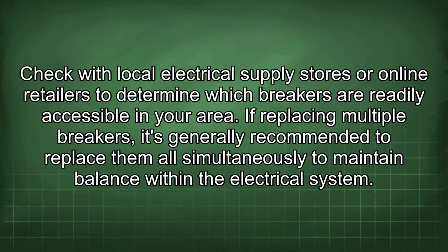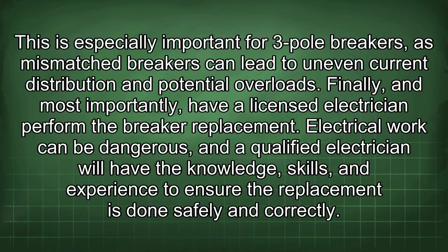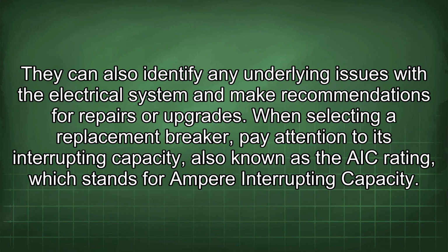Check with local electrical supply stores or online retailers to determine which breakers are readily accessible in your area. If replacing multiple breakers, it's generally recommended to replace them all simultaneously to maintain balance within the electrical system. This is especially important for 3-pole breakers, as mismatched breakers can lead to uneven current distribution and potential overloads. Finally, and most importantly, have a licensed electrician perform the breaker replacement. Electrical work can be dangerous, and a qualified electrician will have the knowledge, skills, and experience to ensure the replacement is done safely and correctly. They can also identify any underlying issues with the electrical system and make recommendations for repairs or upgrades.